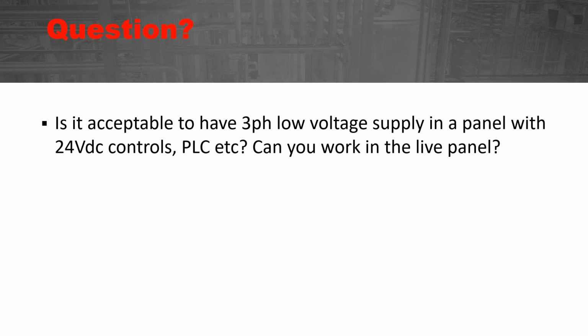I think, Charlie, I will give my input on the first part, which I think from the 508A standards, you can have a three-phase supply in a panel where you have 24 volts DC controls, as long as you have a completely separated or isolated three-phase low voltage supply, which is, I'm assuming, 480 volts in this case. You need to be completely isolated from your 24 volts DC circuits. And if you're having that, then you need to make sure that specific circuit is locked out and it's de-energized before it feeds anything to this low voltage compartment. And then in that case, you can work live. However, if it is not, then it has to be completely de-energized before you work on the panel. What do you think, Charlie?